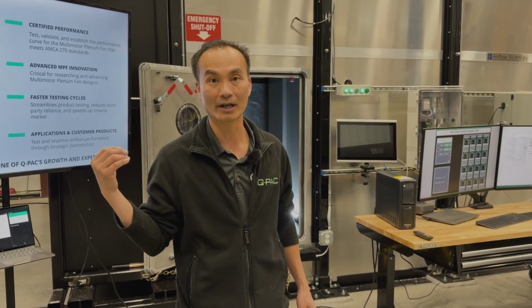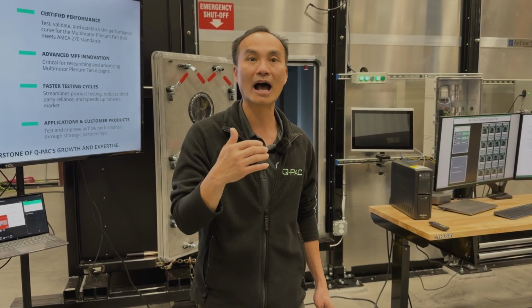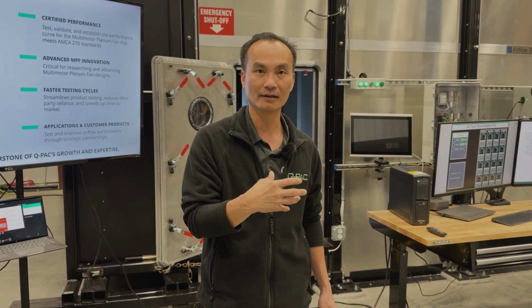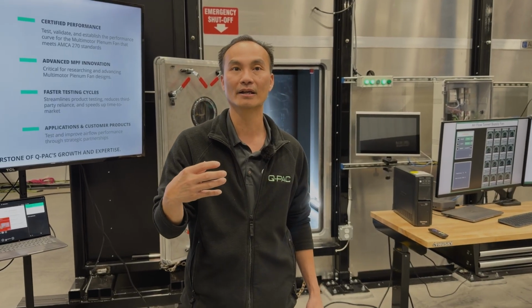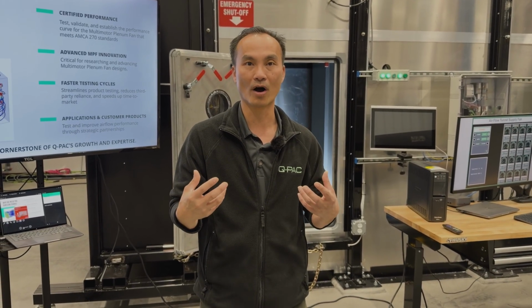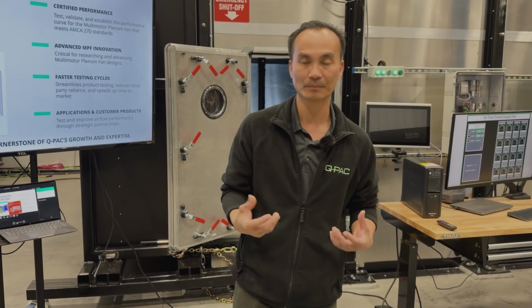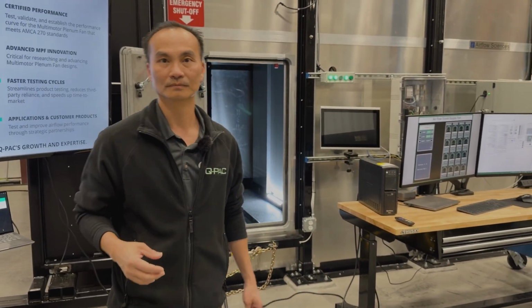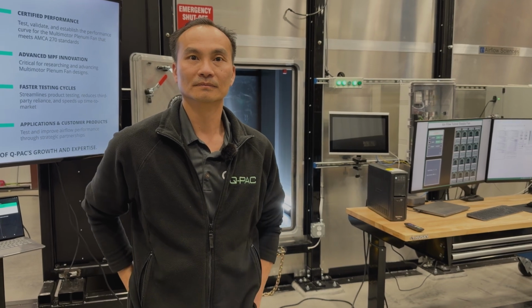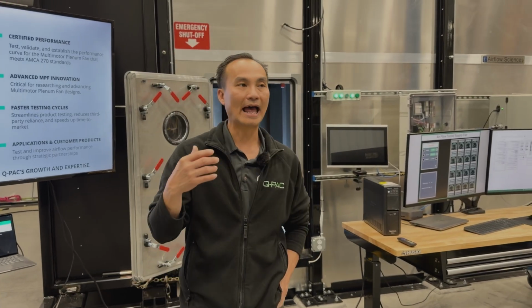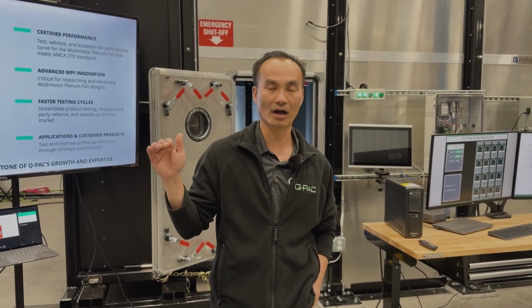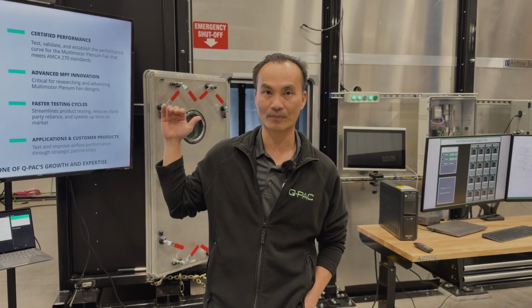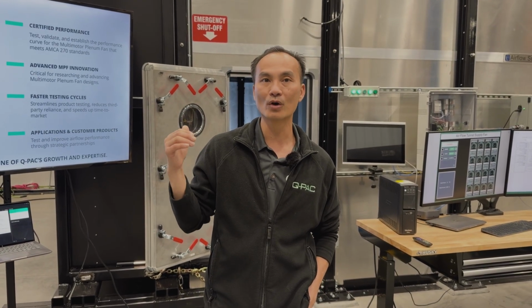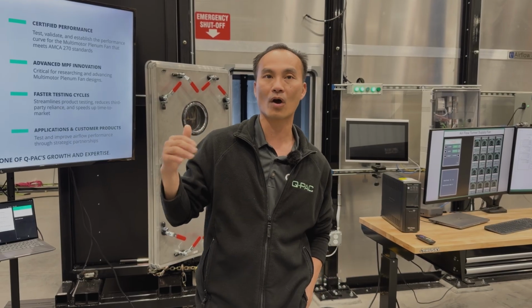But if you don't have the capability to test it, right now everybody basically just relies on the single fan performance, and then they kind of estimate the overall performance of the fan array or an MPF. Right, so now you're saying we're certifying total systems, and not only that, it will have a stamp on it that says this is legitimate data, it's not us blowing smoke or guessing. Absolutely, yes. That's awesome. So that is the basic certification and accreditation of the airflow tunnel. But the real thing is we are building this to build our better product into the future.